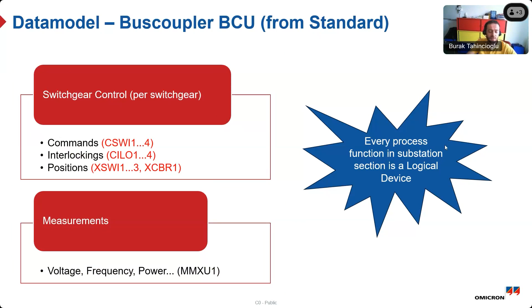Okay, the next thing what we need to really keep an eye on is for creating a data model of a virtual IED or in any IED, we would have two things. Yeah, we have this hierarchy. You might be familiar with physical device in the top level. You have the IED here, and then the logical device could be many functions or a combination of many functions coming together as a logical device, which can be freely defined by the user. And then we have each function as logical node.